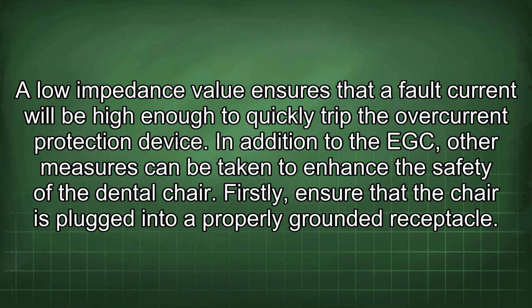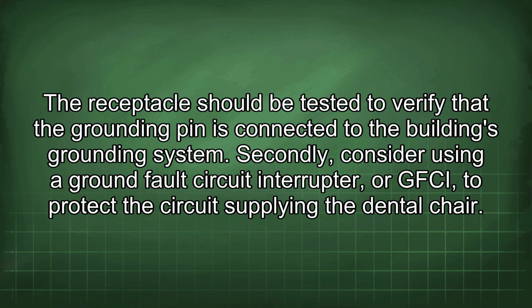A low impedance value ensures that a fault current will be high enough to quickly trip the overcurrent protection device. In addition to the EGC, other measures can be taken to enhance the safety of the dental chair. Firstly, ensure that the chair is plugged into a properly grounded receptacle. The receptacle should be tested to verify that the grounding pin is connected to the building's grounding system.